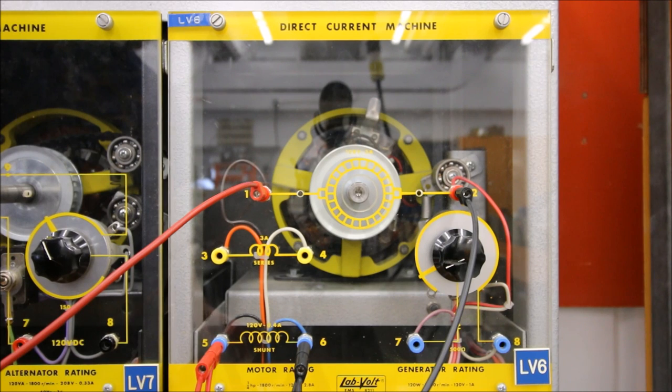Sounds good. It sounds totally different than the series motor. This one's got really good speed regulation, and you can see that it essentially stays at the same speed. It doesn't take off like the series motor did before.